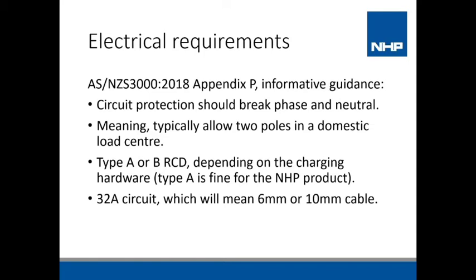A type B RCD detects this. So if the EV charging equipment can't handle DC fault current detection, you should be looking at a type B RCD upstream. If the EV charger can handle DC fault current detection, then you only need a type A RCD upstream. Anyone who's looked at various different RCD types will know that type B RCDs are far less commonly used and they are more expensive. So one of the gotchas in this industry is when you're installing EV chargers, look for one that can handle DC fault current because it'll make your install cheaper. I'll put my salesman's hat on very firmly here and say the NHP equipment can certainly support a type A in this context.